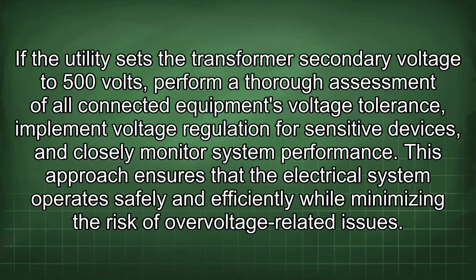If the utility sets the transformer secondary voltage to 500 volts, perform a thorough assessment of all connected equipment's voltage tolerance, implement voltage regulation for sensitive devices, and closely monitor system performance. This approach ensures that the electrical system operates safely and efficiently while minimizing the risk of overvoltage-related issues.